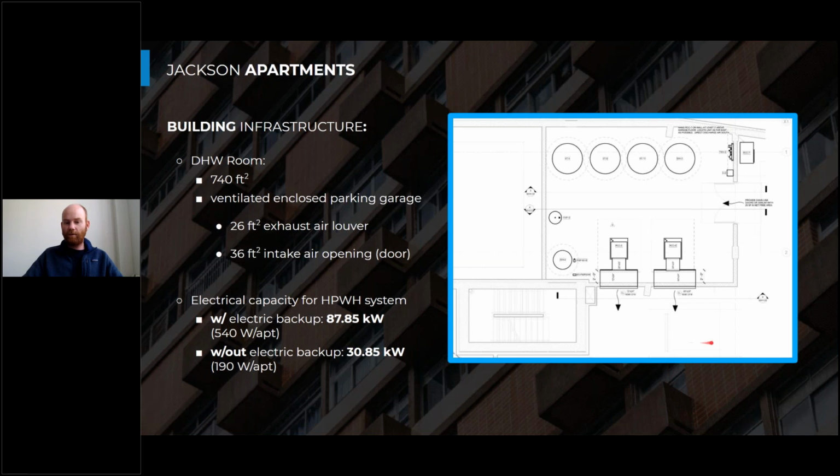And this has worked really well. It operated last year, even during the snowstorm. We were moving heat into that water with our heat pump water heaters. So one more very successful story here. We've implemented this design approach in at least 10 Seattle buildings, and all of them have operated well and smoothly, with a few exceptions that were easily corrected later on.